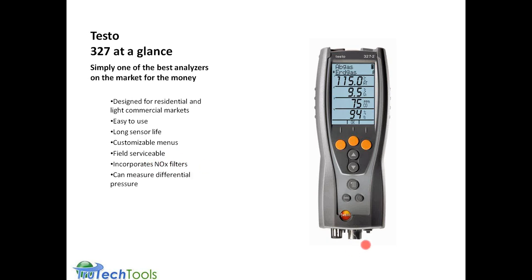You can measure differential pressure with the inboard pressure sensor that's inside the meter, and differential temperature between the two sensor probes in the unit, and we'll get into where those are located exactly. And you can print results with the optional printer. And again, we recommend printed results because they're a record. It's something you can have.